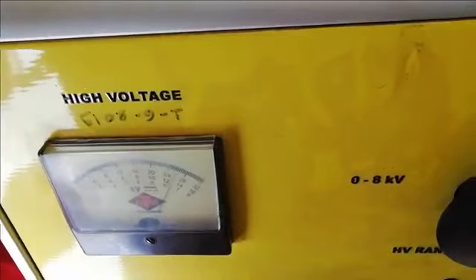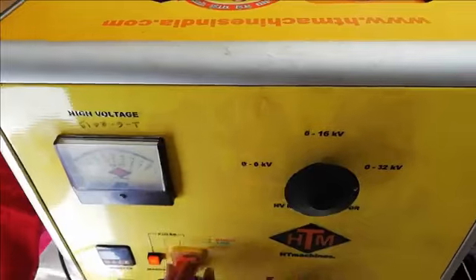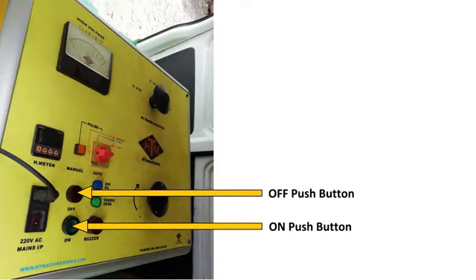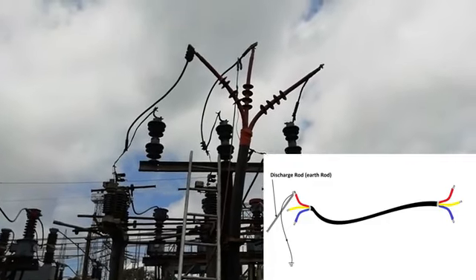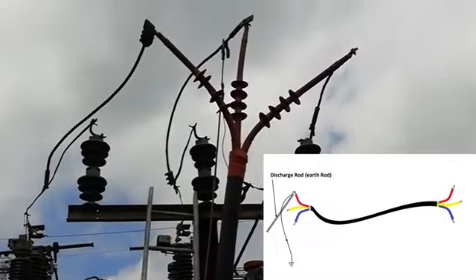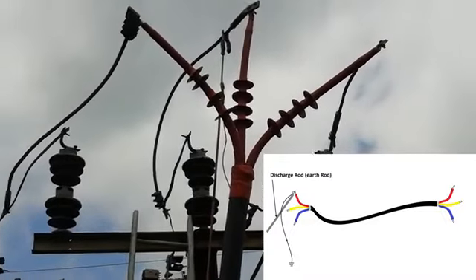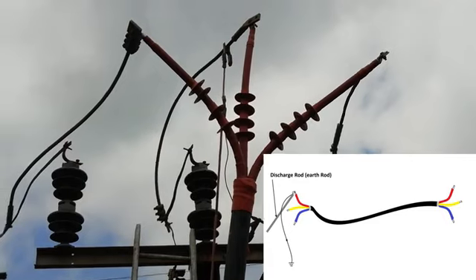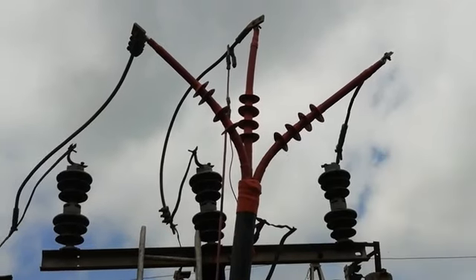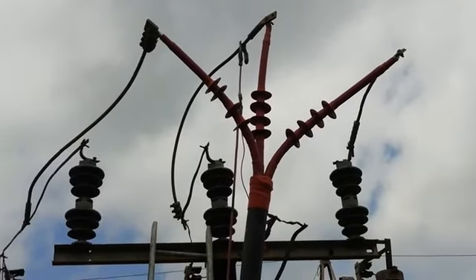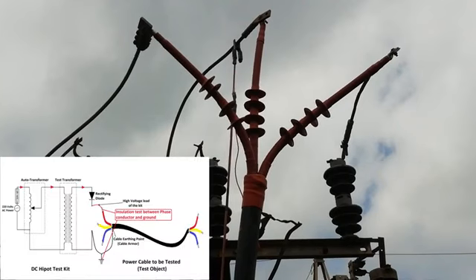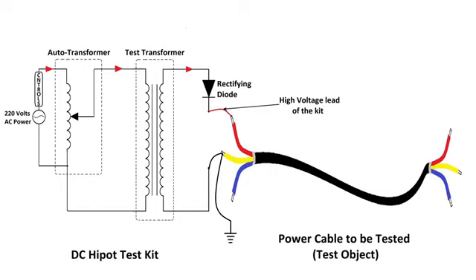Once the test is done, the voltage is brought down to 0 using the knob. The off button is pressed, and the phase conductor of the cable which is tested is discharged carefully using the earth rod so that there are no residual charges on that conductor and it becomes safe to work. The same procedure is repeated for the other 2 phases of the cable. This way we can check the healthiness of insulation between phase and earth. To check insulation healthiness between 2 phases, the high voltage lead is connected to one phase and the other lead is connected to the other phase and ground.